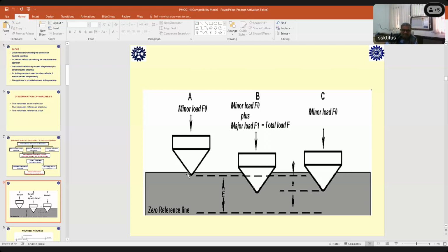So it uses an indenter. The indenter is a very integral part of any hardness machine, I have already mentioned. So what kind of indenter is used in this particular hardness? In Rockwell hardness, generally a conical indenter is used. So you can see here the indenter is a conical indenter. It can sometimes be a diamond indenter or it can be a ball indenter. There are two types of indenter, we'll come to that. For the diamond indenter, the conical angle has to be 120 degrees plus or minus 0.1 for the calibration machine. We'll come to the geometrical part and the requirements a little later.